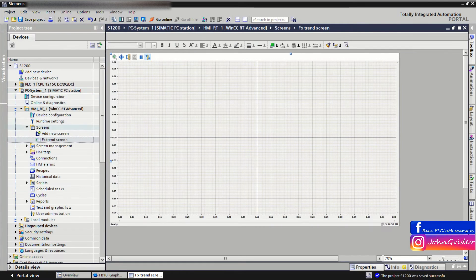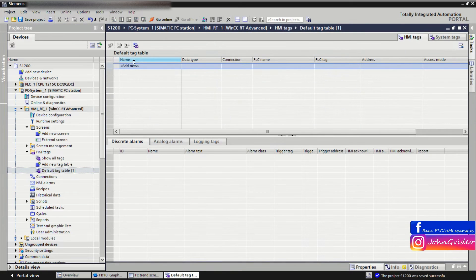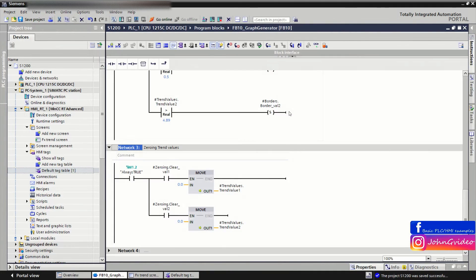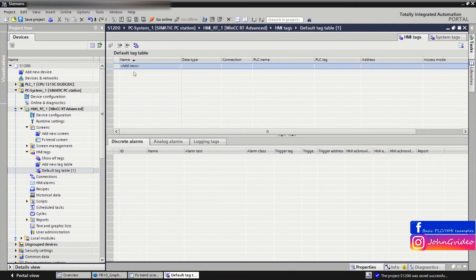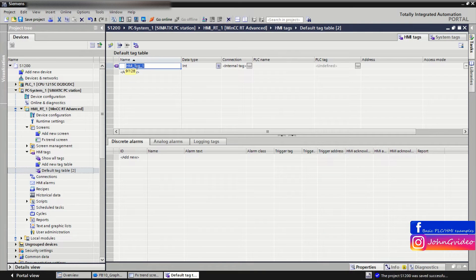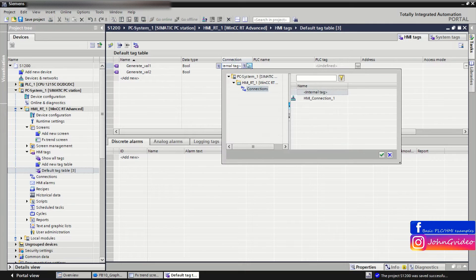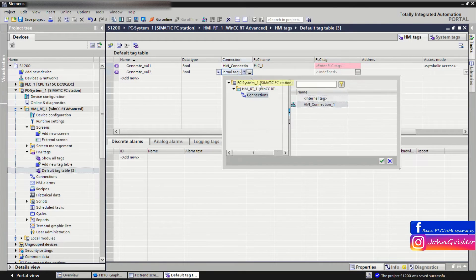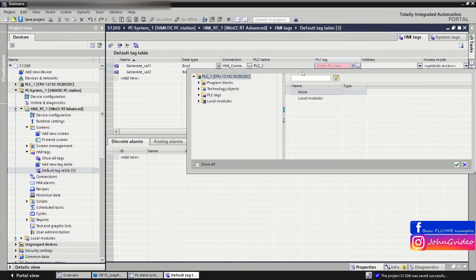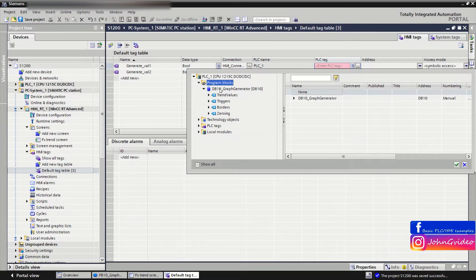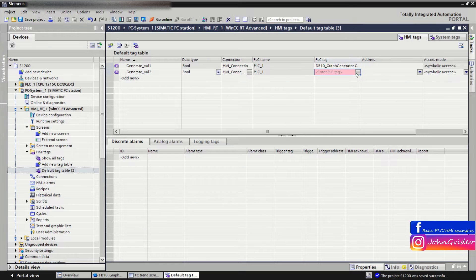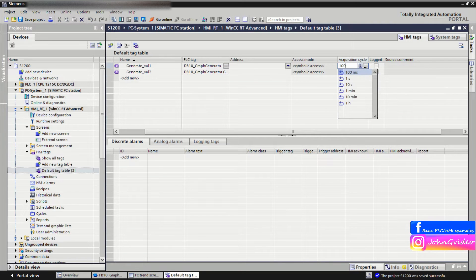Now we create the external HMI tags and link them to the HMI. The first will be 'Generate Value 1' of data type Bool, and the second 'Generate Value 2' also of data type Bool. These are external tags — here we insert the HMI connection with the PLC and link the tags from DB10: generate value 1 and generate value 2, with an acquisition cycle of 100 milliseconds.